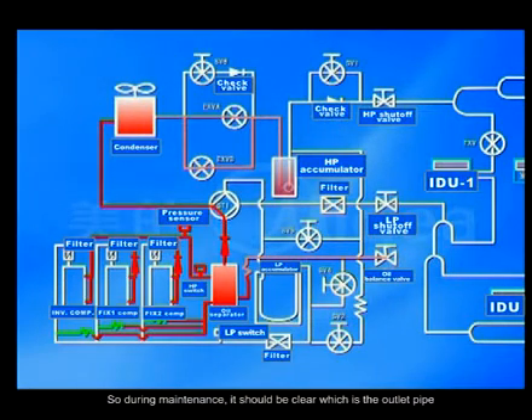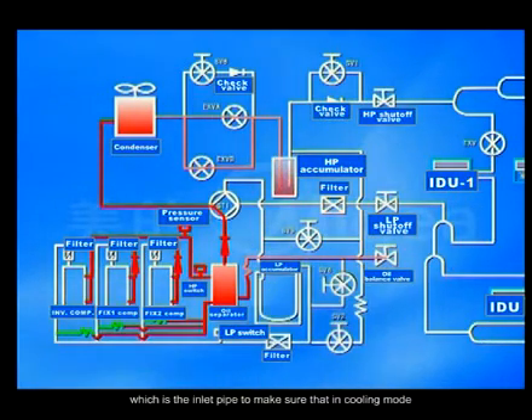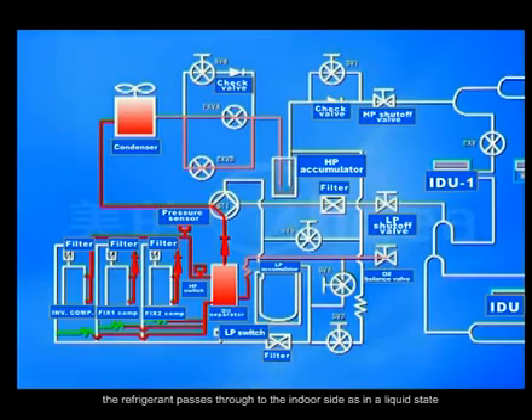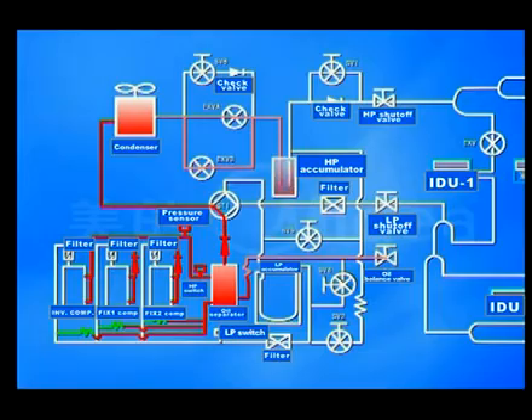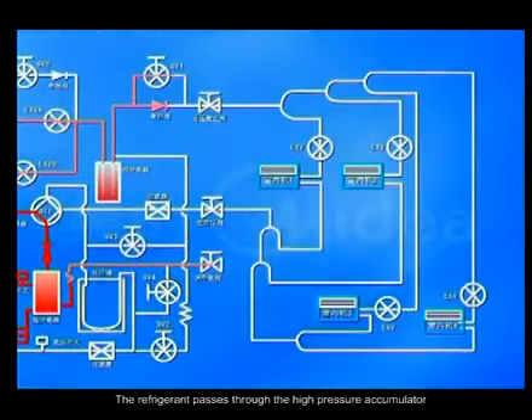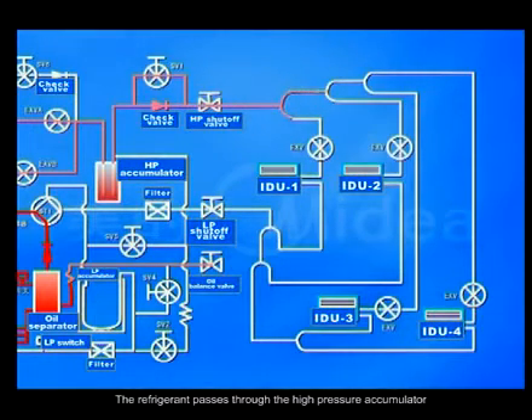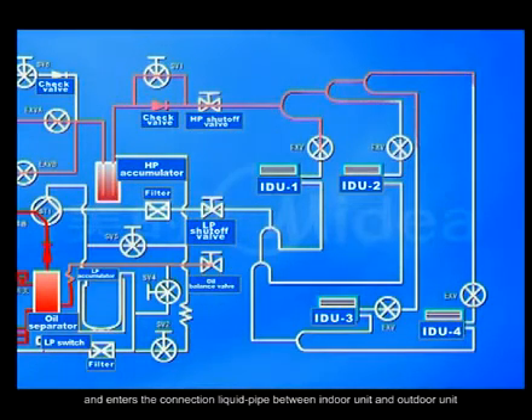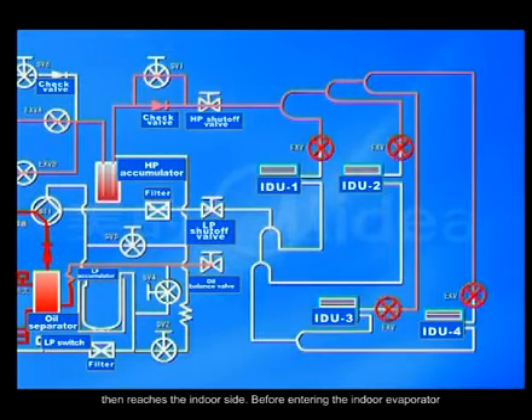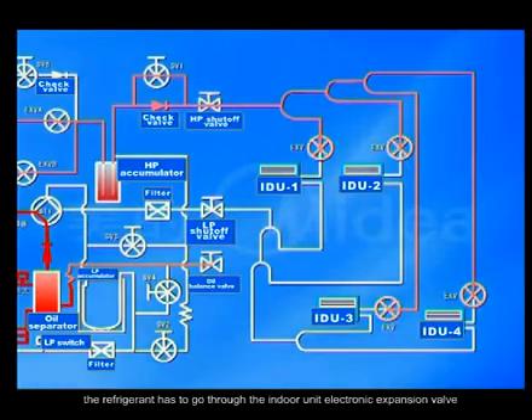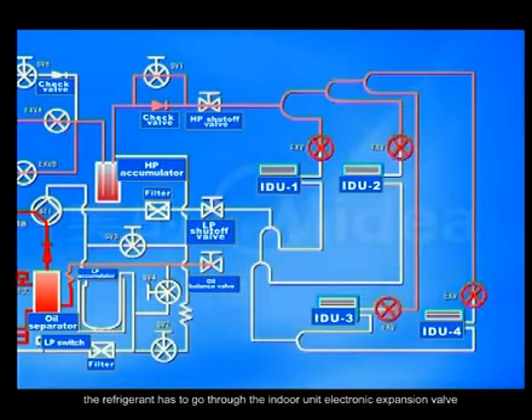So, during maintenance, it should be clear which is the outlet pipe, which is the inlet pipe, to make sure that in cooling mode the refrigerant passes to the indoor side in a liquid state. The refrigerant passes through the high-pressure accumulator and enters the connection liquid pipe between indoor unit and outdoor unit, then reaches the indoor side. Before entering the indoor evaporator, the refrigerant has to go through the indoor unit electronic expansion valve for throttle and pressure reduction.